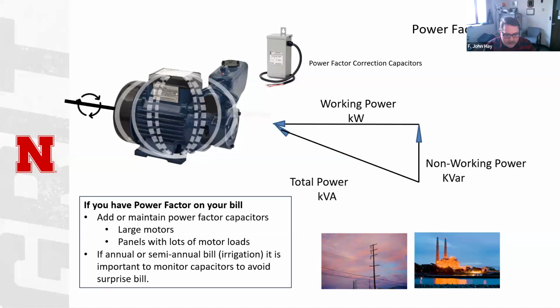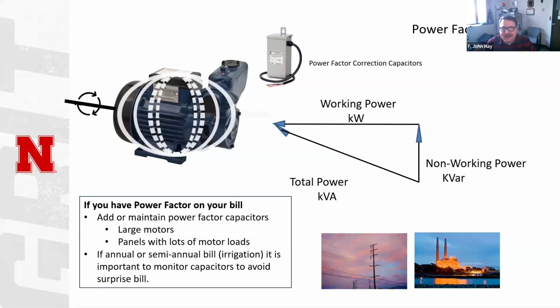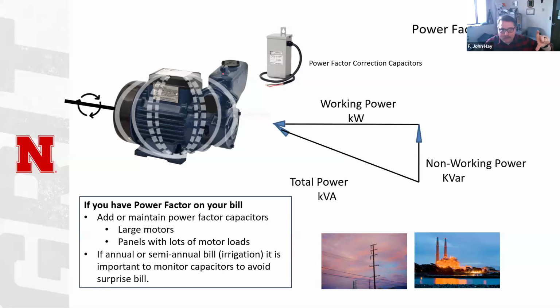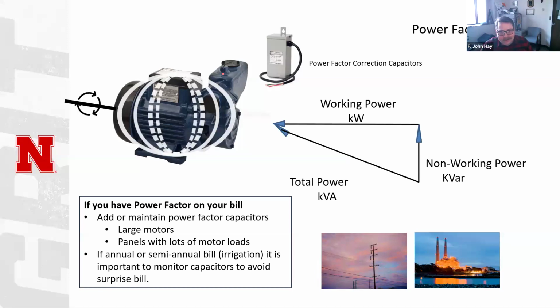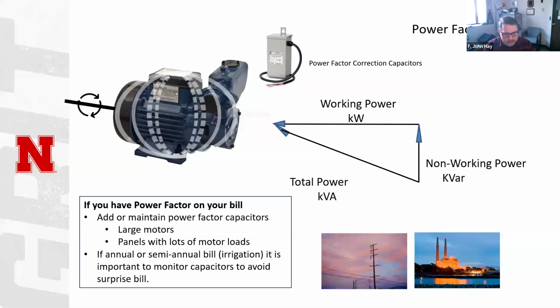So monitoring those is going to be interesting because it's just a box. There's nothing that tells us it's on. And the power factor on our meter isn't in real time. It is the power factor at the peak, back at that demand peak time, which may have been set a month ago. So we don't have that real-time power factor. The utility might, and you could call them and ask for it, but we don't. Many customers aren't going to have that real-time power factor to see if that power factor correction is working. So just something to think about.